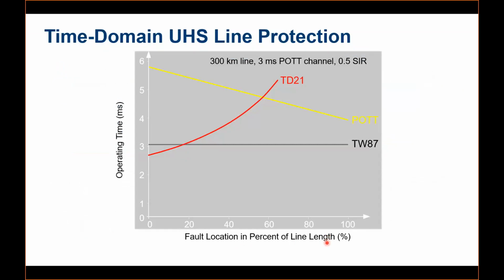So this is a graphical representation for the permissive overreaching transfer trip scheme, with a half of source-to-impedance ratio. You can see TW87 is the most consistent. It's at 3 milliseconds, and POTT schemes are also pretty fast, depending on the channel that you are using. If the channel is slower, that time will be added. And TD21 is again dependent on the location of the fault. For up to the middle of the line, it's much faster, and you can achieve about 4 times faster as compared to the conventional distance element.